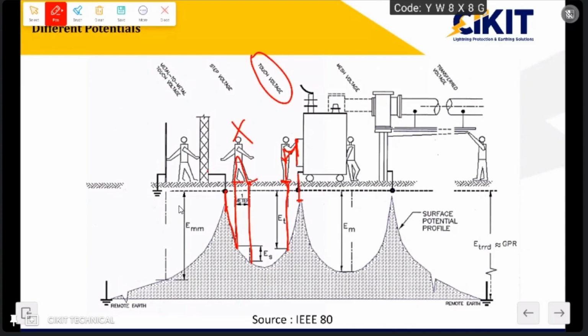We have to clearly observe one thing: the first criterion for current to flow is a difference in potential. If two objects are maintained at the same potential, then there won't be any current flow. Whenever there is a difference in potential, the current will flow from higher potential to lower potential. The same thing is happening here. If the two feet are maintained at the same potential, there won't be any current flow. That is the reason if you are working in any substation, you should not run inside the substation. At the same time, you should ensure that there is very little distance between the two feet so that the step voltage will be much lower.